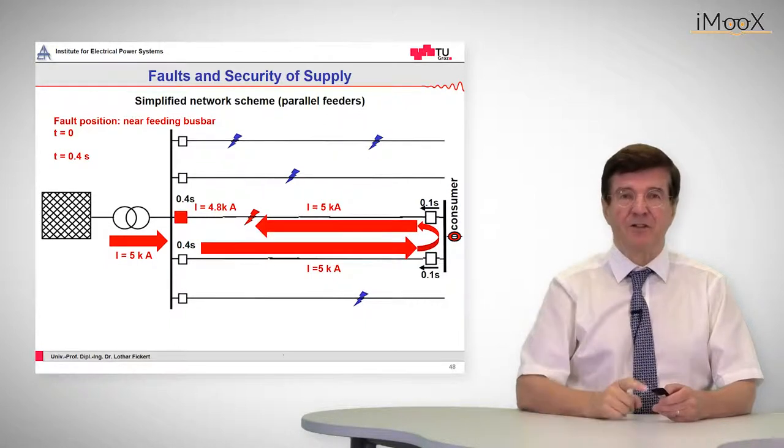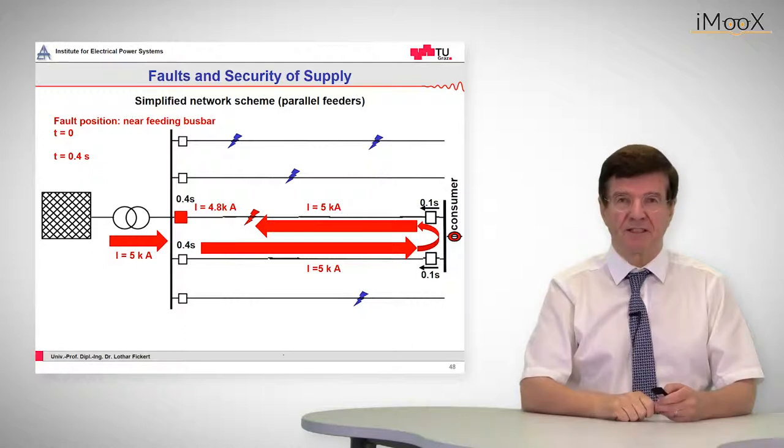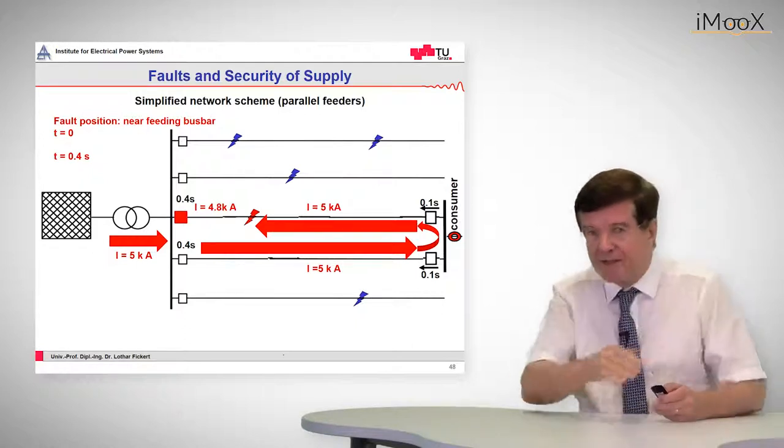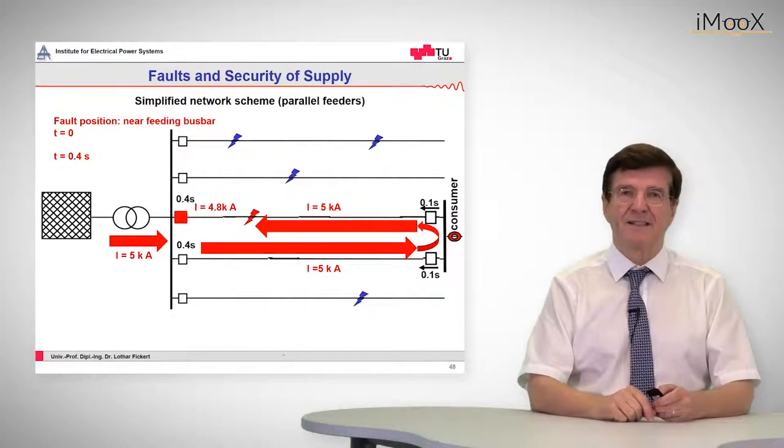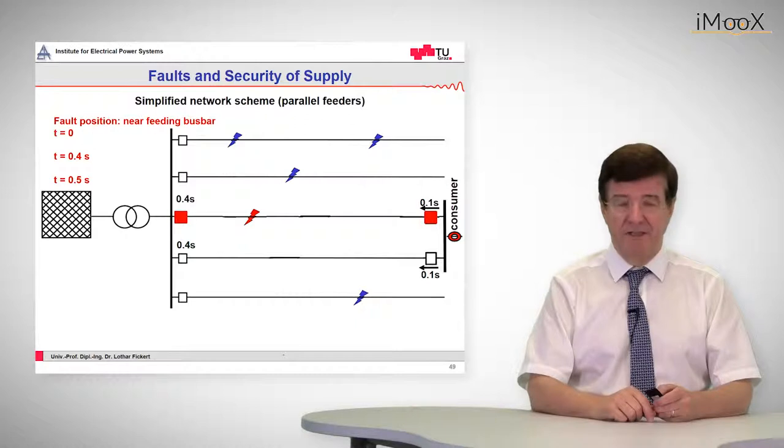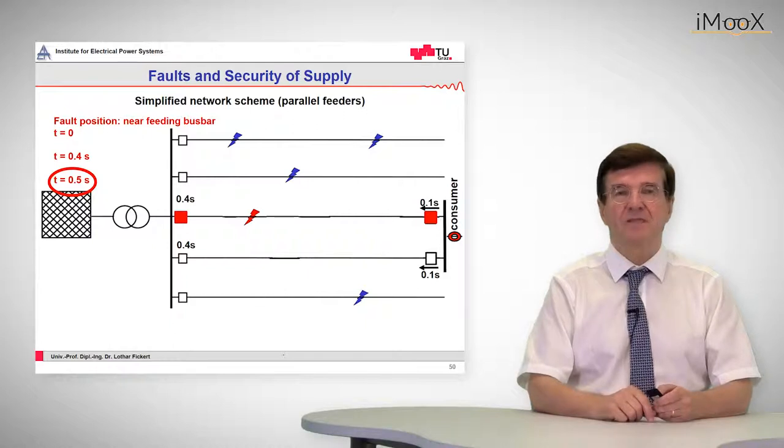It will trip after 0.4 seconds and at that very moment the short circuit will come the other way around. That means now the relays that sense this increased current will pick up and after one additional 0.1 second the second relay will trip out. So the whole clearing time now is 0.5 seconds.